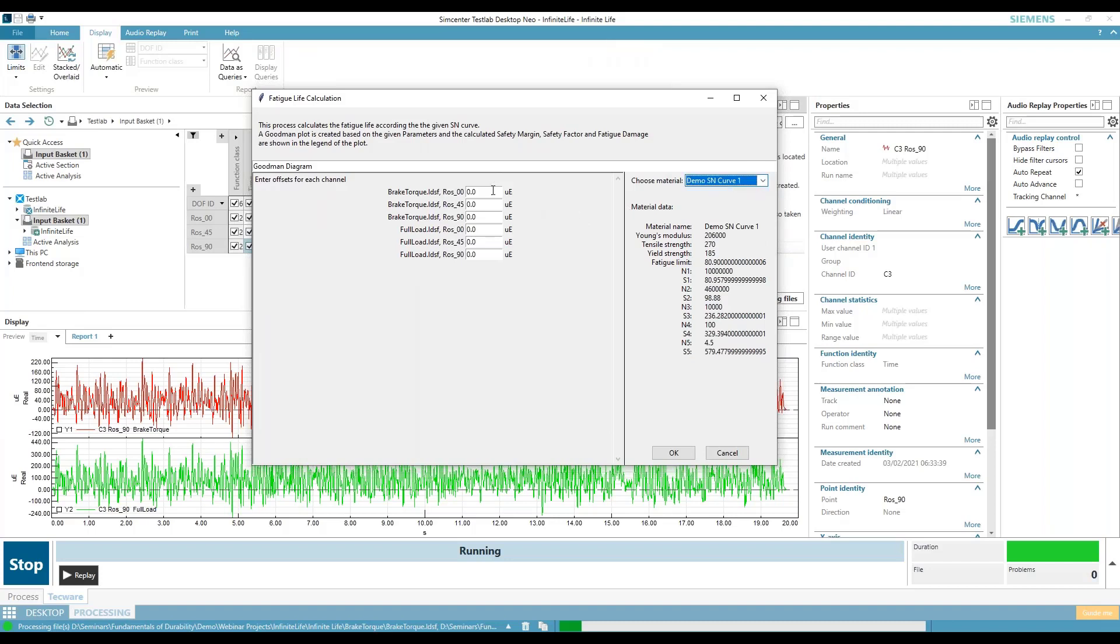If I want to add an offset, some people balance their gauges all the time, so there is no mean in their gauges and they record an assembly strain. Some people add that assembly strain back in and then run this. If they didn't add it back in, you could type it in here.